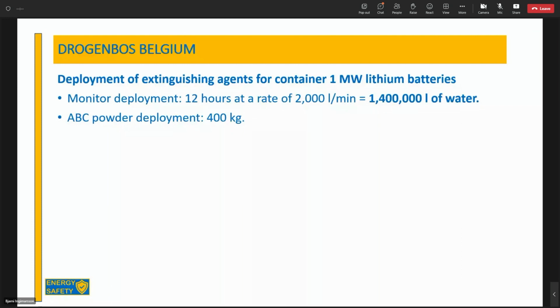So I say to the manufacturers, think about this. You can extinguish any fire with a glass of water if you're quick enough. And sometimes you cannot let it burn out, if such a container is near facilities where a lot of people live, you cannot do that. So it will not always be possible to let it burn out. For me, extinguishment at cell level may cost more, but it's needed.